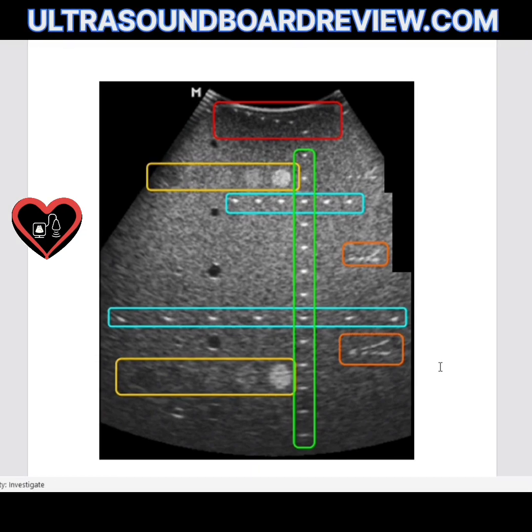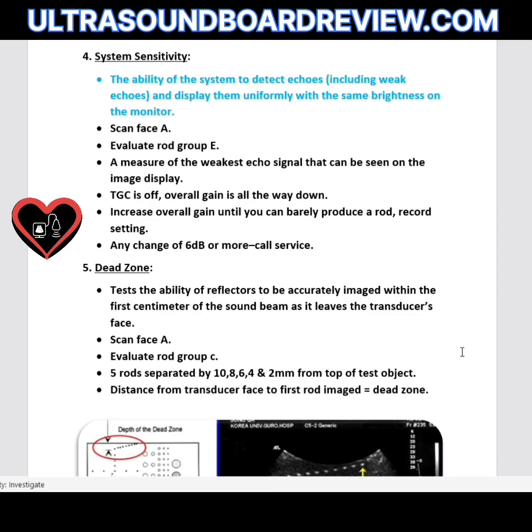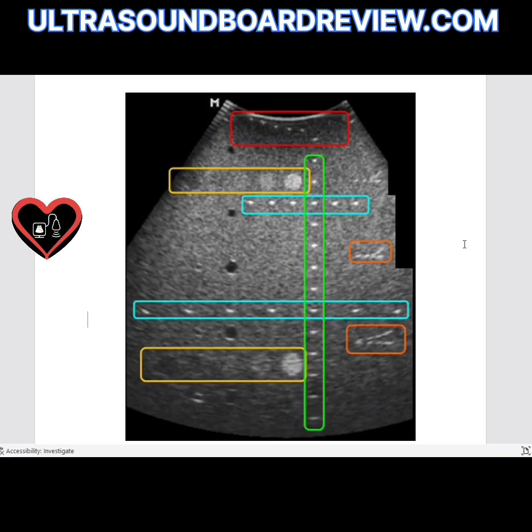What is the dead zone? The dead zone tests the ability of the transducer to accurately image within the first centimeter of the sound beam. In this phantom, the area circled in red represents the dead zone, and this will test the ability of reflectors to be accurately imaged within the first centimeter as the sound wave exits the face of the transducer.